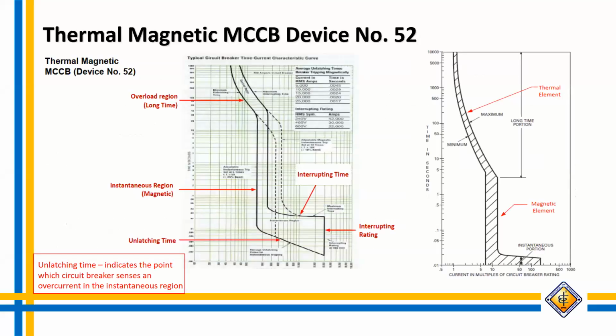So basically, here's the thermal magnetic MCCB trip characteristic. As you can see here, we have the overload region, the long time. This represents the long duration that the circuit breaker can withstand. And we have also the instantaneous or the magnetic. We have the interrupting time and interrupting rating. And we have the unlatching time. Unlatching time indicates the point at which the circuit breaker senses an overcurrent in the instantaneous region. We have the thermal element. The other figure represents the thermal element and the magnetic element of MCCB.